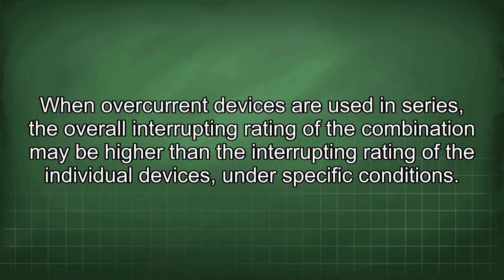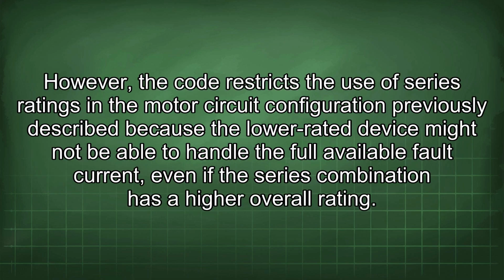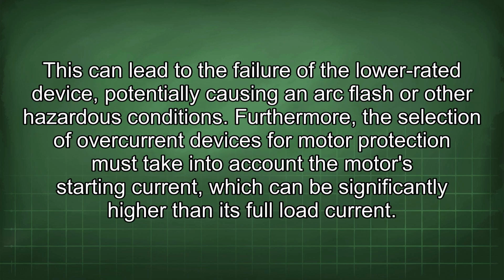When overcurrent devices are used in series, the overall interrupting rating of the combination may be higher than the interrupting rating of the individual devices, under specific conditions. However, the code restricts the use of series ratings in the motor circuit configuration previously described because the lower rated device might not be able to handle the full available fault current, even if the series combination has a higher overall rating. This can lead to the failure of the lower-rated device, potentially causing an arc flash or other hazardous conditions.